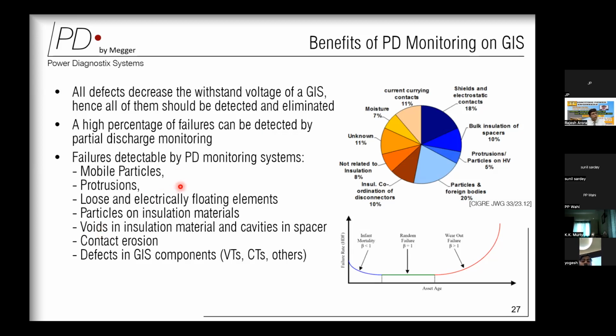So the failures which can be detected by PD monitoring are mobile or moving particles, the protrusion, loose or floating element inside the GIS, particles on insulating material, if there are some dust particles onto the insulating material, voids in insulating material or the cavities inside the spacers, contact erosion, or defects in GIS components such as VTs, CVTs, or any other. And if we see these defects, they are either visible during the commissioning or the early years of operation, or they will start appearing during the old age or wherever the wearing of GIS happens. Generally, the GIS is quite stable unless some unfortunate event happens during the continuous operation period.